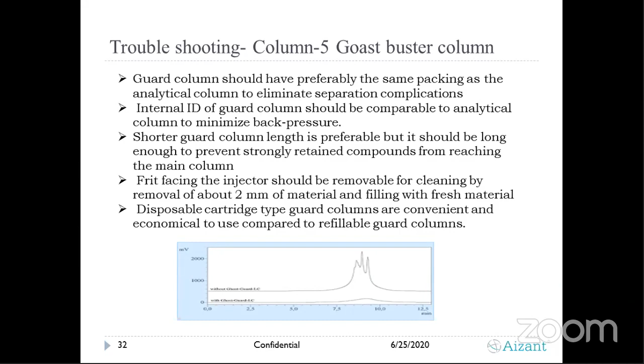So my recommendation is that if you are facing such challenges in your blank, very specifically in gradient analysis, please try to use this Ghostbuster column, which can resolve your issue. And it is better to use a guard column where your sample matrix is highly viscous or the matrix load is very high, very specifically for formulation matrices. I can give an example of suspensions where we are preparing samples of 2 grams or 3 grams in 10 ml, and the sample is very dirty. To clean up, it is better to use a guard column so your column can be saved.